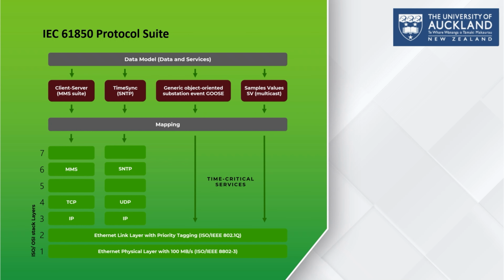The middle section labeled mapping shows how each type of service is associated with its corresponding communication protocol. MMS traffic is mapped to the MMS protocol, SNTP uses the SNTP protocol, and both run over IP networks. However, GOOSE and SV are mapped directly to the Ethernet layer instead of TCP/IP because they require extremely low latency and deterministic delivery for protection applications. So this mapping ensures that each service type is transported in the most efficient way based on the time-critical requirements.